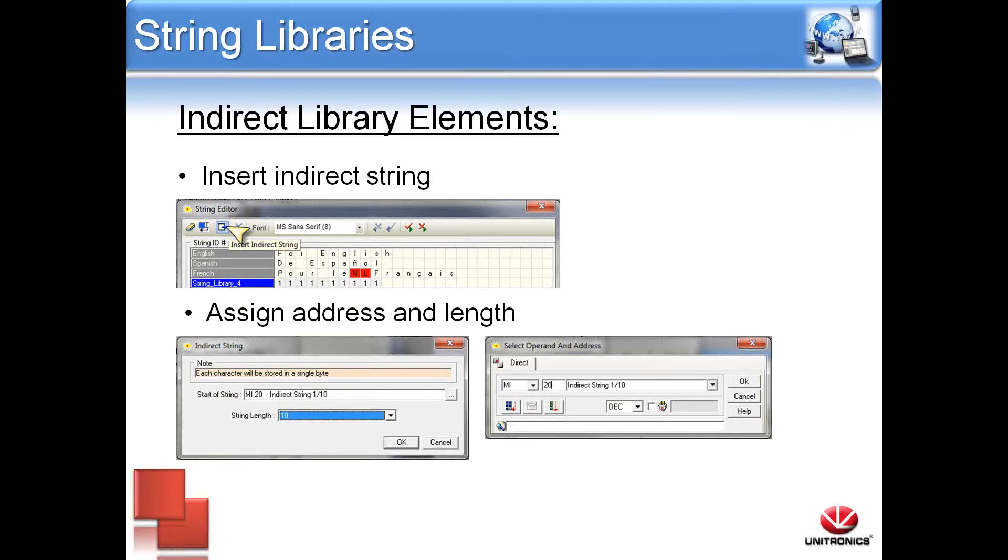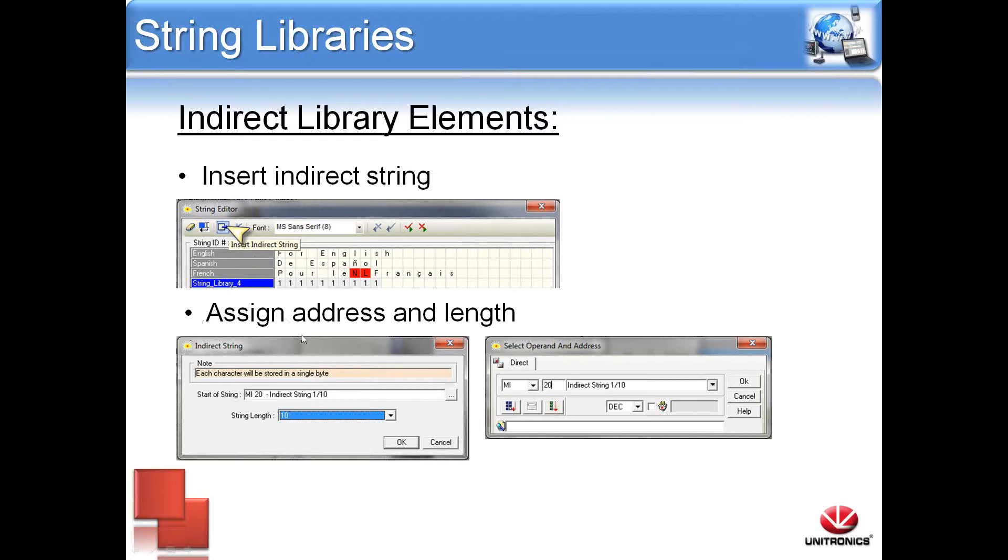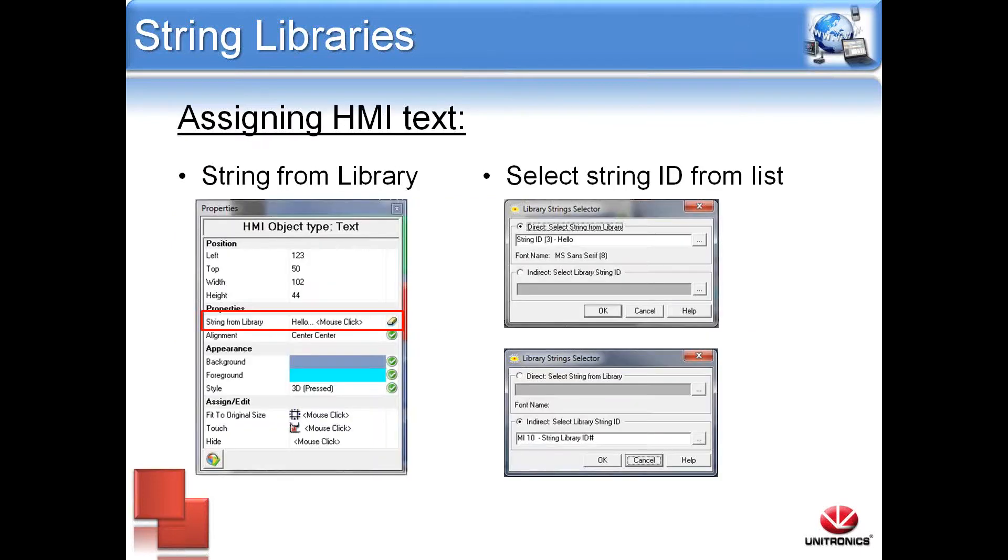You can also assign indirect library elements. Indirect addressing can be used in conjunction with static text. All you need to do is assign an address and a vector length. Here I've selected insert indirect string into string library 4. I've assigned an operand address MI 20 and length of 10. The indirect text variable will display as a vector of numerals corresponding to how many variables are being used.